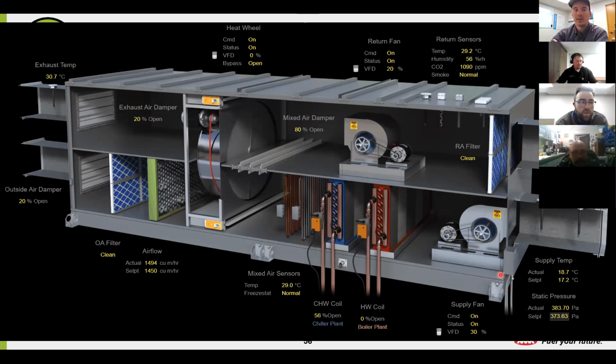The way I'll walk through this is I'll start here at the return air. This is coming back from the building. We go through a set of filters that's going to clean that air. And then we go through the fan, and there's a couple of different things that can happen here. You'll see in this picture that our exhaust air damper is 20% open. So there's going to be a need to relieve some air from the space. That's all air that's going to be put outside. We're exhausting it from the building.